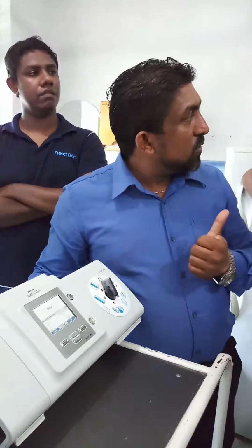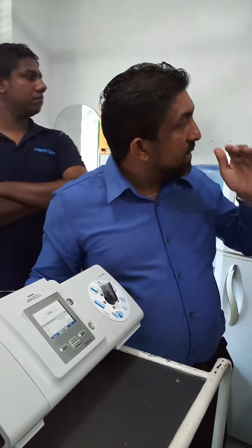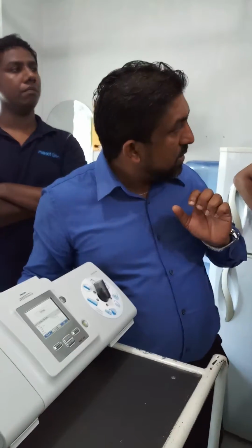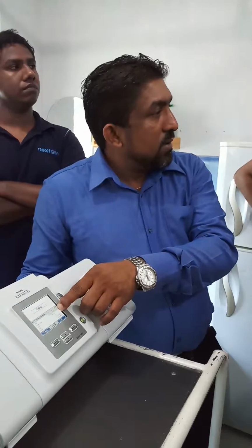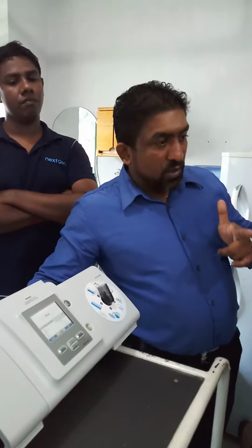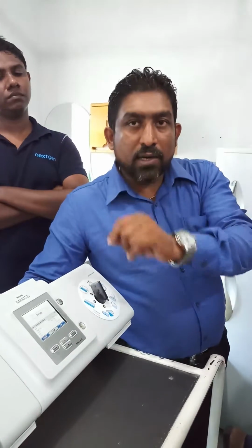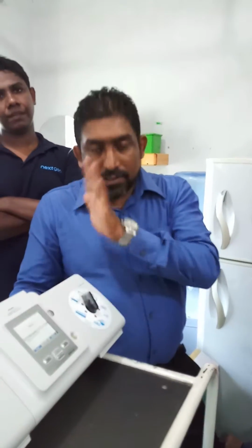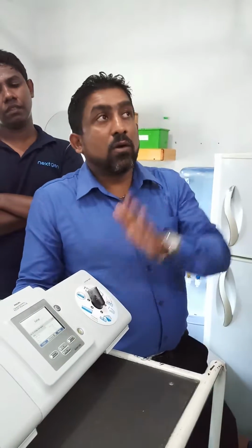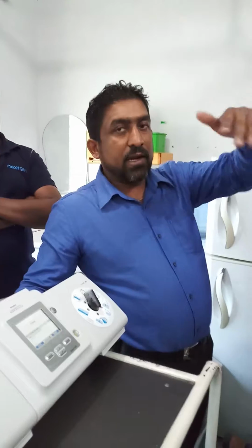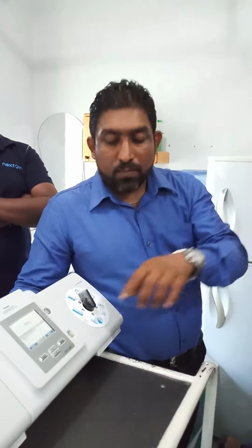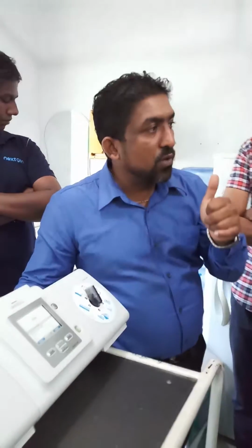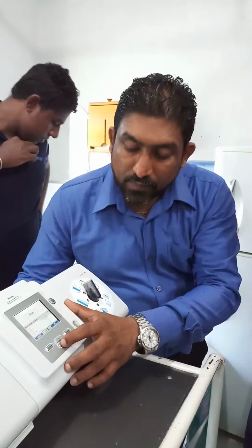ST mode. ST mode is the same as SIMV mode. That is on the bigger ventilators, they call it SIMV mode. SIMV. Do you know? Similar to that, this is ST mode. ST means spontaneous and time mode. If the patient is spontaneously breathing, the machine goes spontaneously. It allows the patient to breathe. And if the patient is not breathing for 1 second or 2 seconds, whatever, it automatically transfers to T mode, time mode. The machine will take the breath. It's like a mini ventilator, no? This is a ventilator, 100% ventilator. Not like the ICU big ventilators, those are big ventilators with volume control and the SIMV mode. But similar to the SIMV mode, the mode is ST mode. Okay, and S mode is there. ST mode.